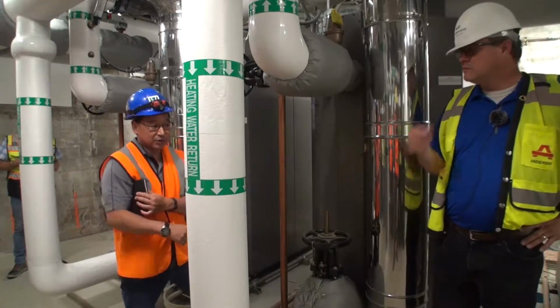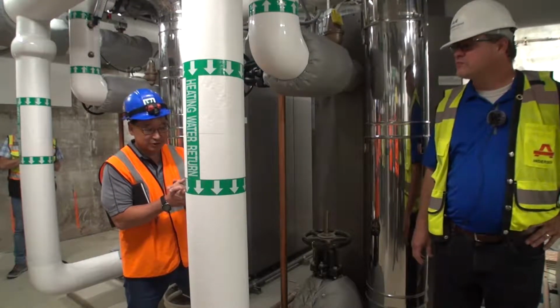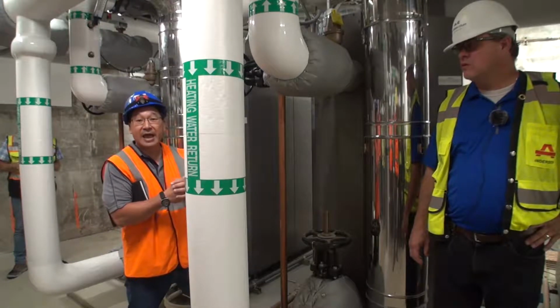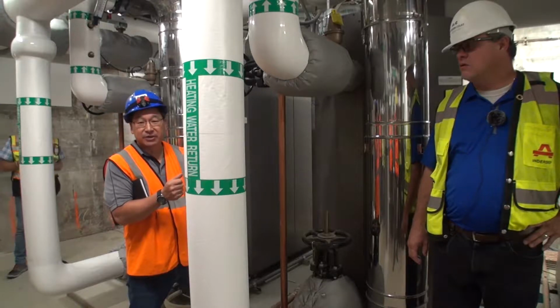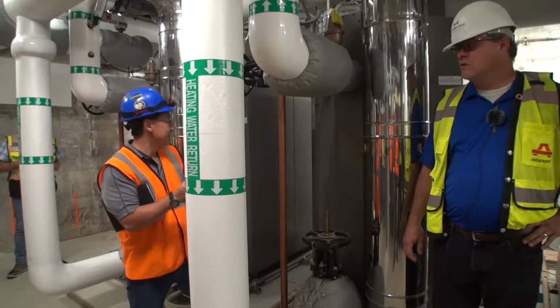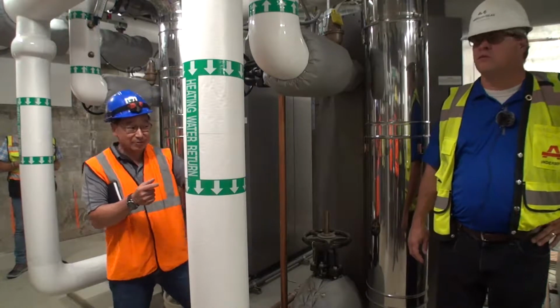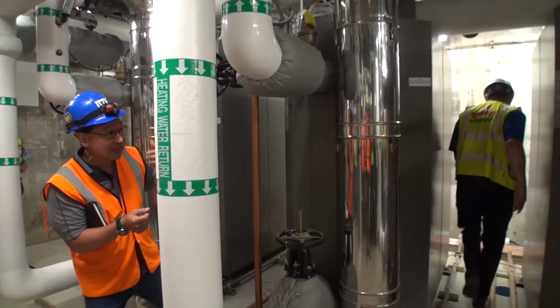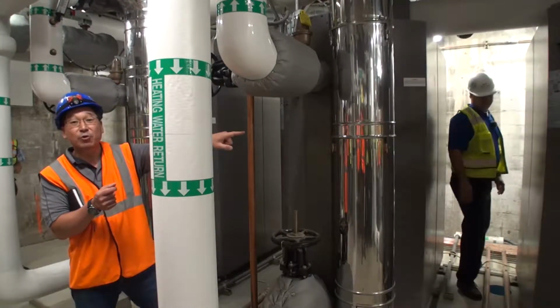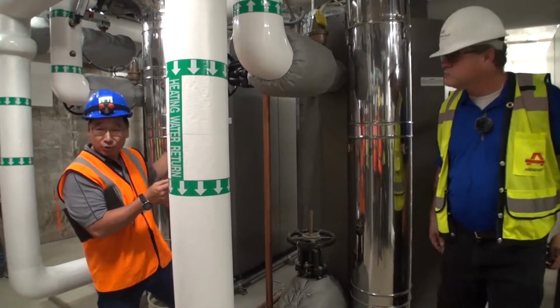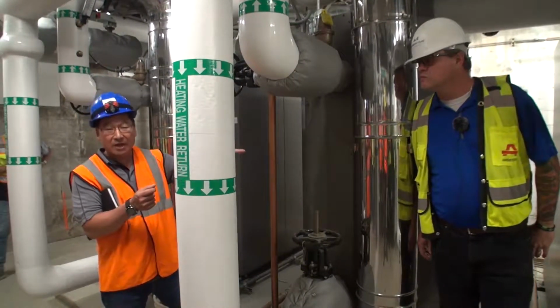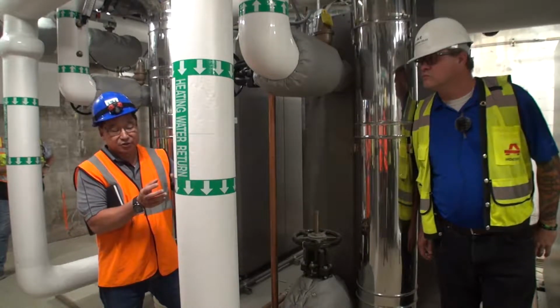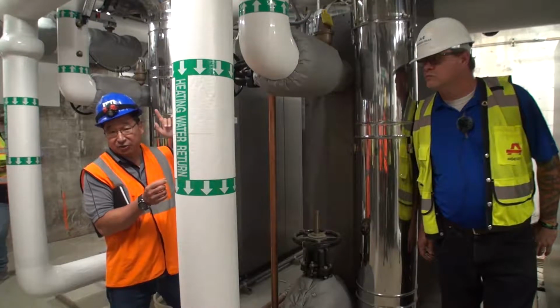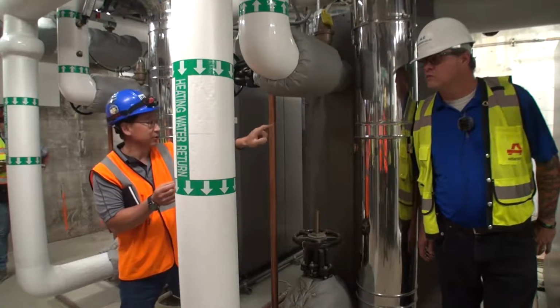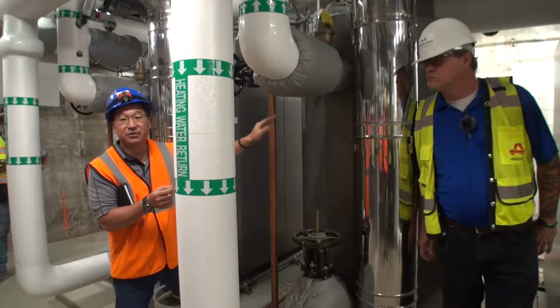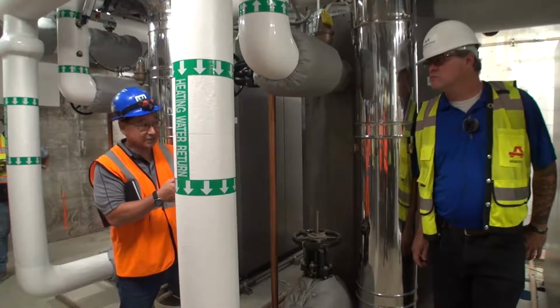If it needs to be locked out, there's another means you can do that. There's another option that we can add later, called an alternate leader. Right now, the boilers have a specific leader. Which is boiler number 1? Is it that one or this one? I don't know, whichever the leader is. Okay, yeah, this is boiler 1. So everything's been programmed to boiler 1 to tell 2 and 3 what to do. If you need to take boiler 1 down, for instance, then there's an option called an alternate leader. You can actually replace the main header sensor. And once you kill power, you kill communication, the alternate leader will take control of the first, the second, and the third boiler. Okay, that's something we can add later.